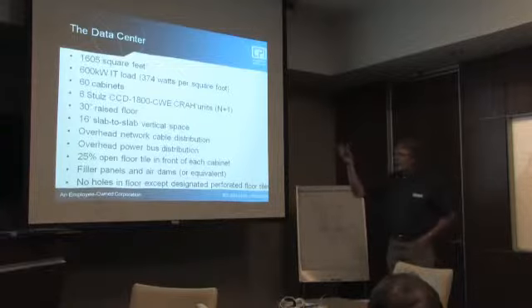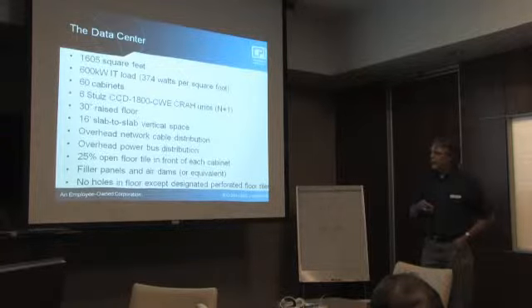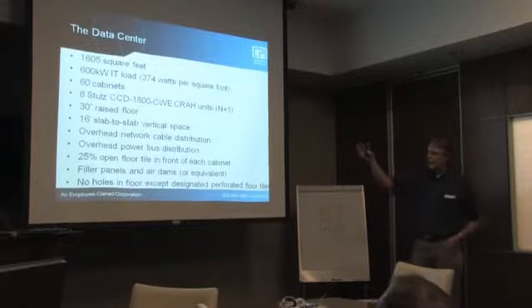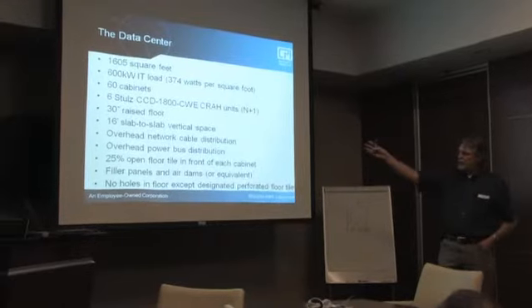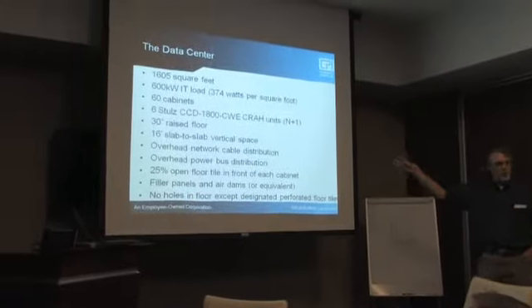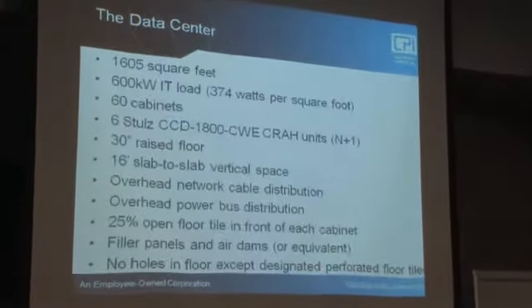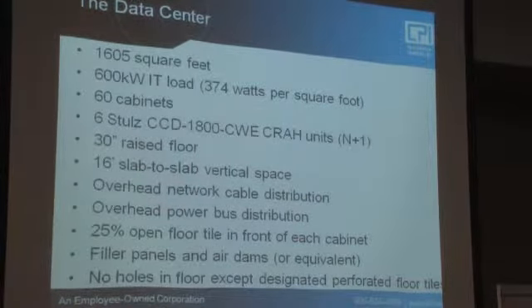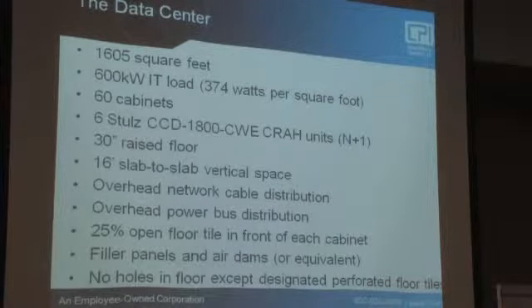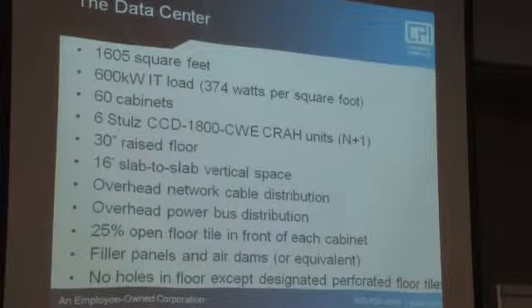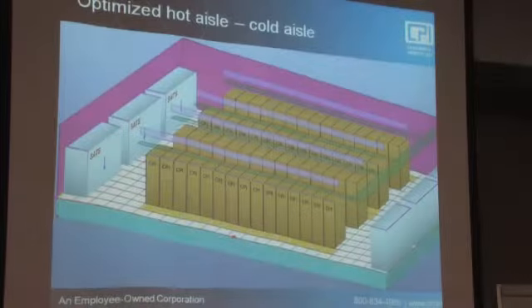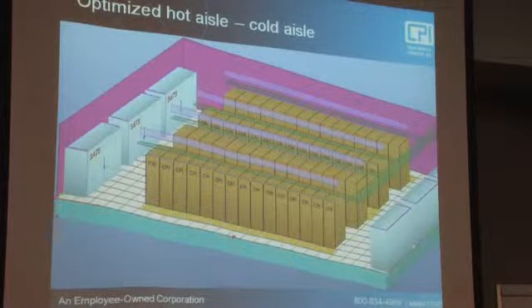The case study has a 1,605 square foot data center with a specific load and number of cabinets. The air handlers were set up with N+1, meaning we thought we needed five, so we've got six in this space. Raised floor and all the particulars of the environment — just the basic layout. The space looks like what was described on that first slide.